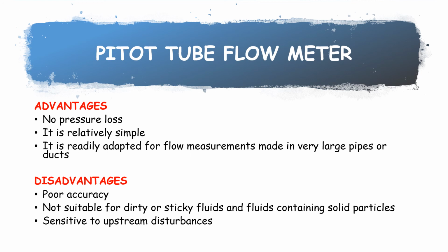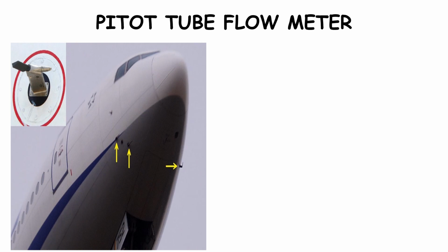Moving on to the advantages and disadvantages. The advantages: no pressure loss, it is relatively simple, and it is readily adapted for flow measurements made in very large pipes or ducts. The disadvantages are poor accuracy, not suitable for dirty or sticky fluids and fluids containing solid particles, and sensitivity to upstream disturbances.